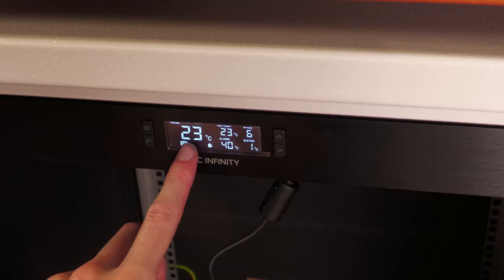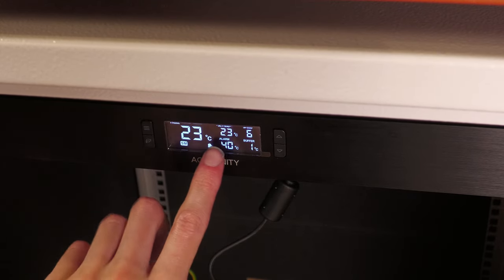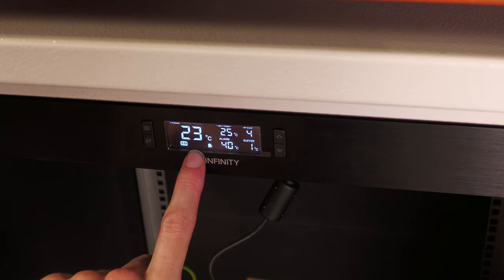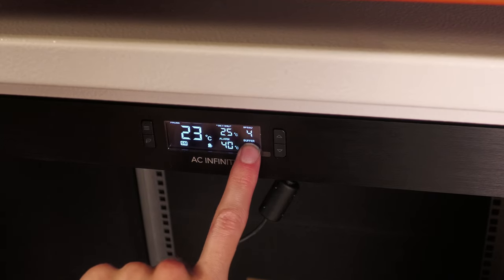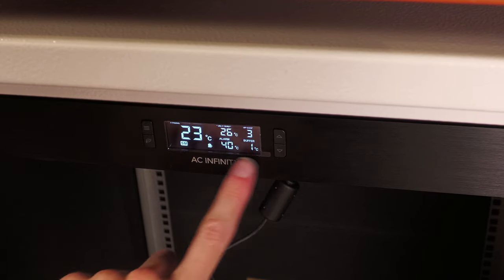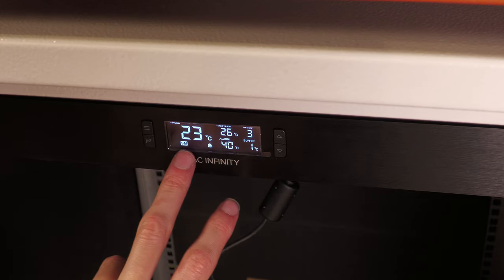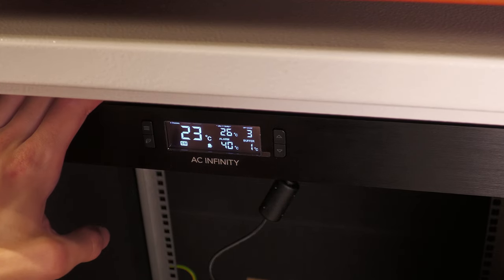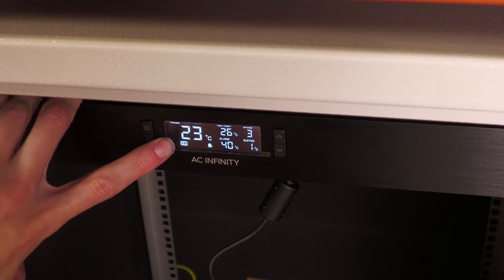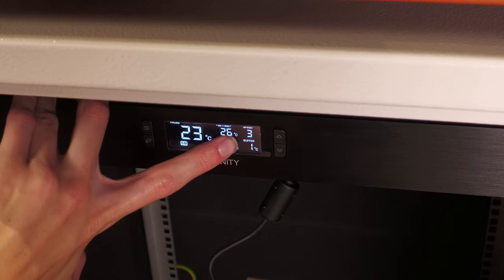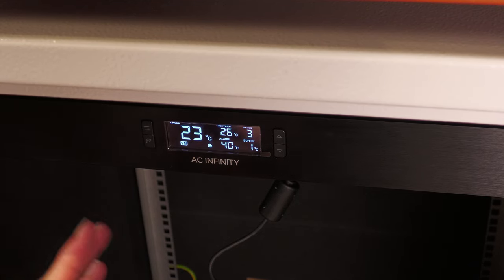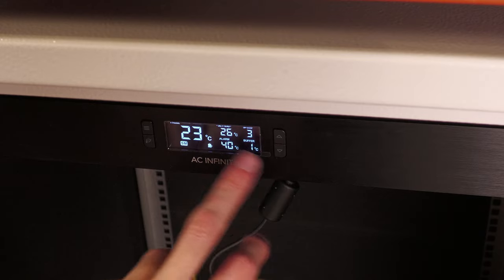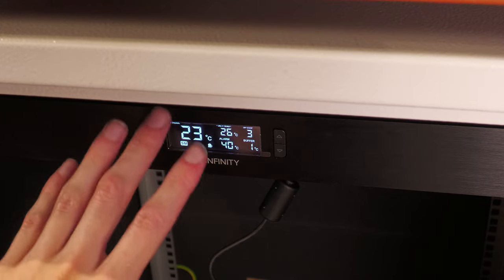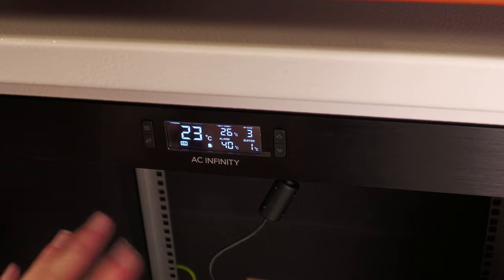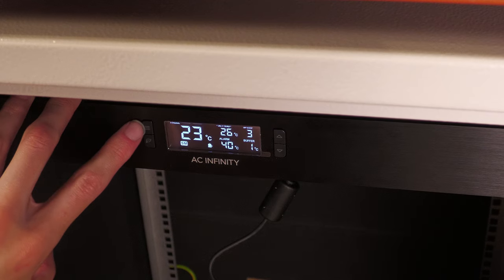The only thing to bear in mind with this is that even if the temperature in the cabinet is slightly below the set temperature, the fans will still run, and they can run at quite high speeds. So you could have a situation where you want the cabinets to stay at 26 degrees, the cabinet's actually 23 degrees, but the fans are running at speed 3, where you might not want the fans running that fast. You might just need to play about and adjust your set temperature to fit the fan speed that you're expecting it to sit around.